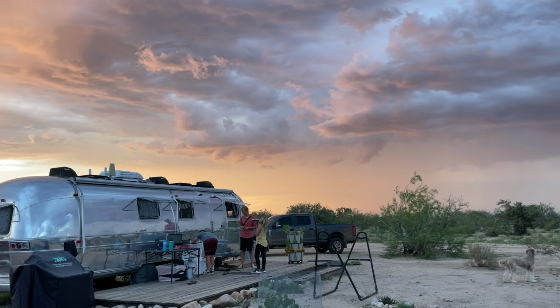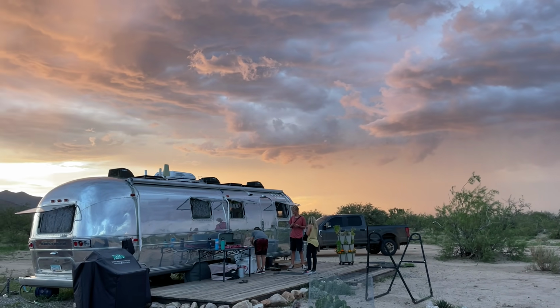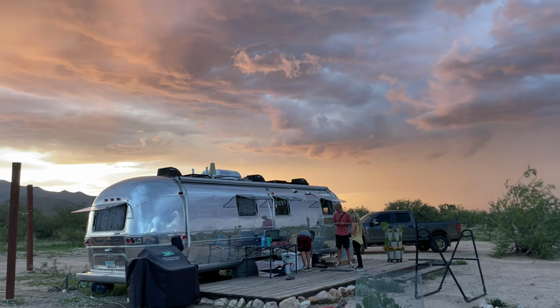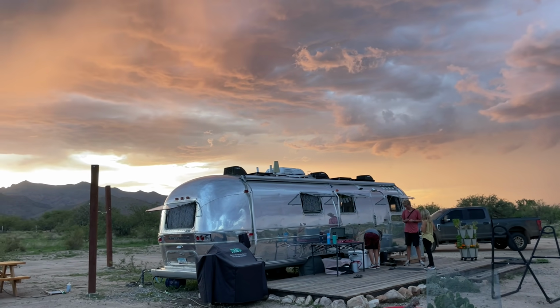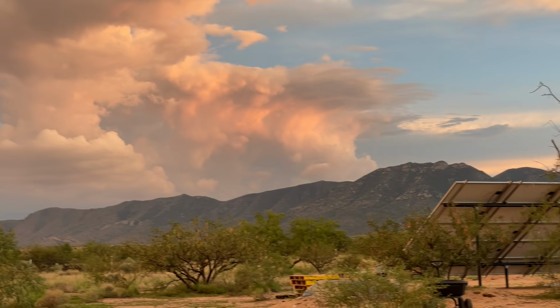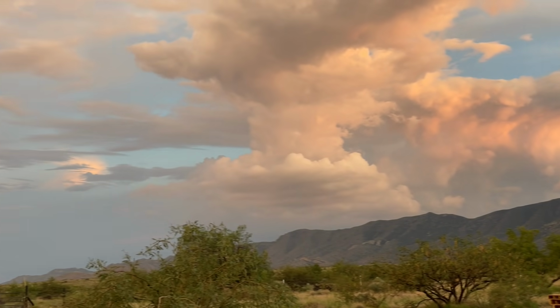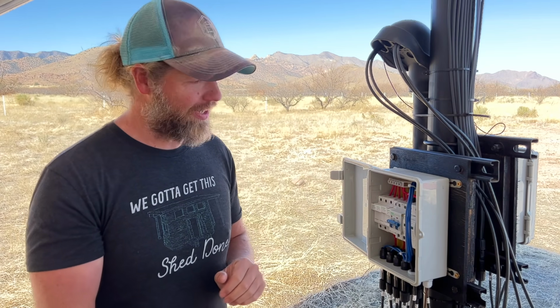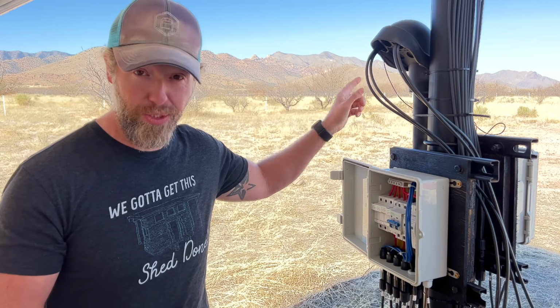The other important thing we needed as part of this install was a lightning arrestor. We hadn't heard of this until we moved out into the wide open spaces of the desert, but apparently indirect lightning strikes are a thing out here, and so just in case this ground mount were to ever get hit by lightning, it would run through this lightning arrestor, it would run to the copper ground rods that we have installed, it would trip, and none of that surge would ever go into the solar shed where all of our gear is.